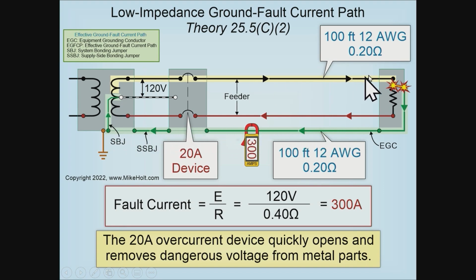Now this path right here, that's the path that Tom's talking about. The impedance of that circuit determines the fault value, or the current value of the circuit. If we knew what the resistance or the impedance of the wire was, and if we knew what the impedance of the fault was, which we don't know, and if we knew what the impedance of the return path back to the source was, let's just assume it was 100 feet of 12 gauge wire in Chapter 9, Table 8, and the code book tells you it's 2 ohms per 1,000 feet, which means it's 0.2 ohms per 100 feet.